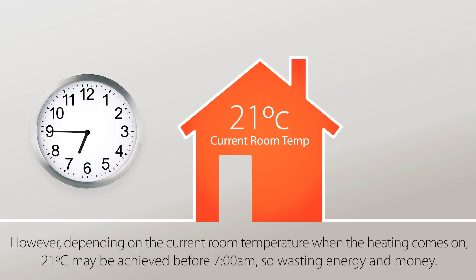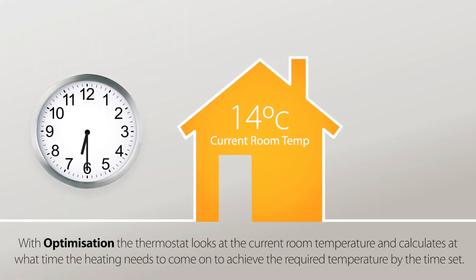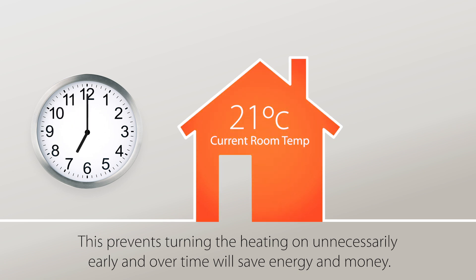However, depending on the current room temperature when the heating comes on, 21 degrees Celsius may be achieved before 7 a.m., so wasting energy and money. With optimization, the thermostat looks at the current room temperature and calculates at what time the heating needs to come on to achieve the required temperature by the time set. This prevents turning the heating on unnecessarily early and over time will save energy and money.